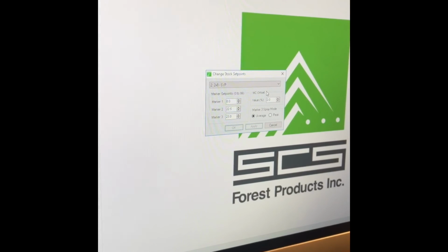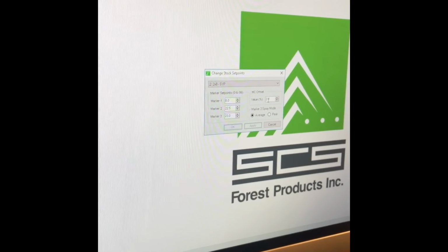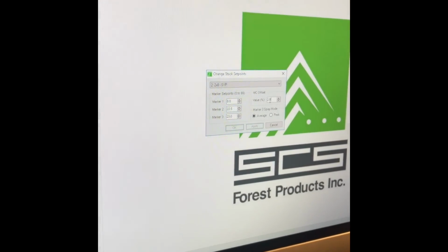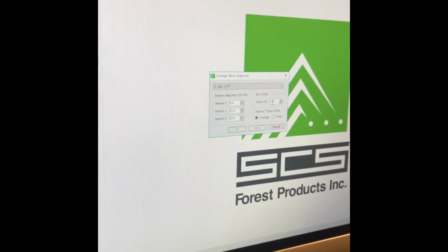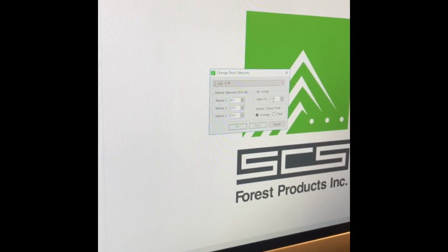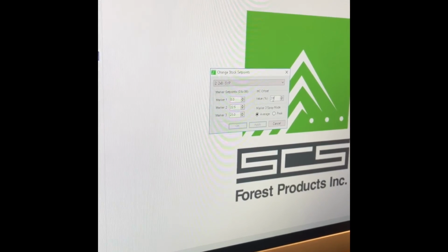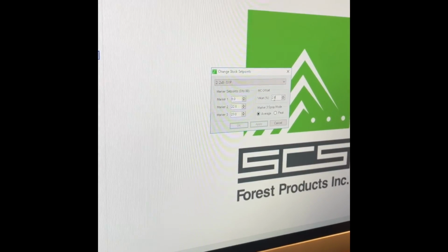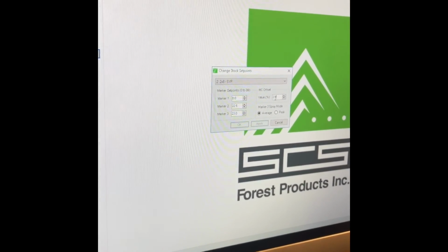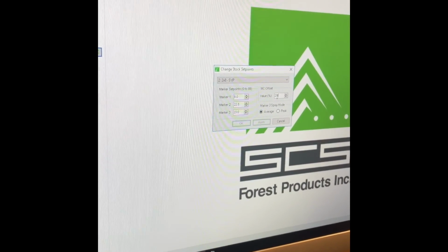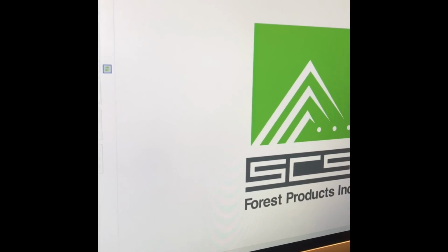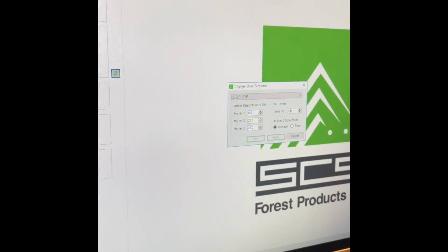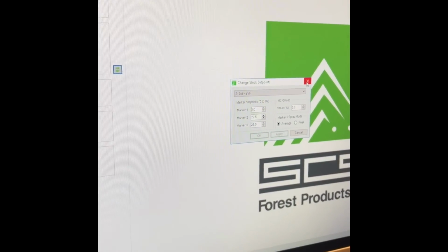The offset here, this is big. If you guys see that it's reading pretty accurate in the sense that it's staying consistently off by a percentage point up or down. So if we were to do a trending line and we were consistently underneath by 1 point, then you would come up here and just subtract 1 point from it, and that would put us right on. It goes the other way around too. You would add if you had to. And that's your target. So that's this little target icon, set points. Change the offset just to get it a little bit closer if you have to.